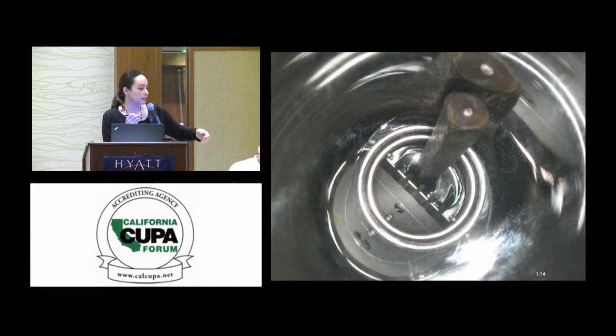I don't know, he let it go there, and he didn't take it out. Now that dipstick is blocking the flapper. Is that flapper going to work? If someone else comes later and starts filling up that tank, there's no good use for that flapper. So that's an easy violation, and that's an easy fix too. They just need to pull that stick out, and that flapper has to be able to move freely and actually shut down.